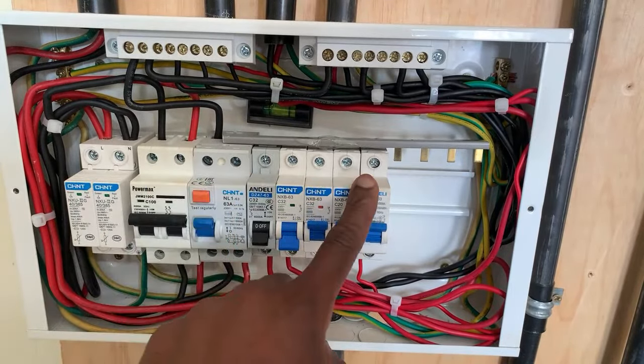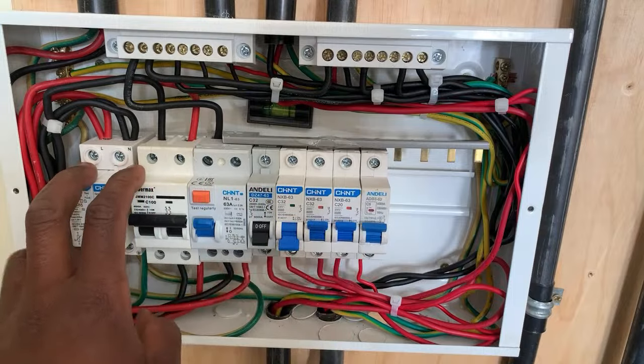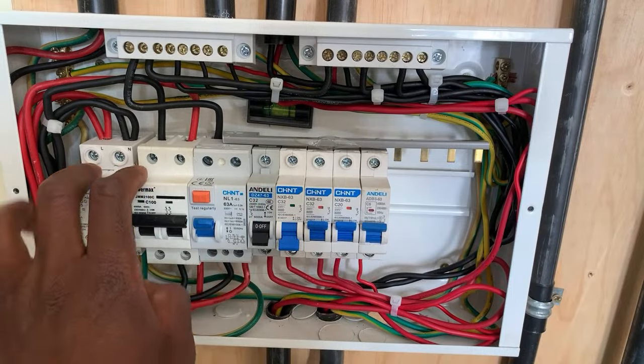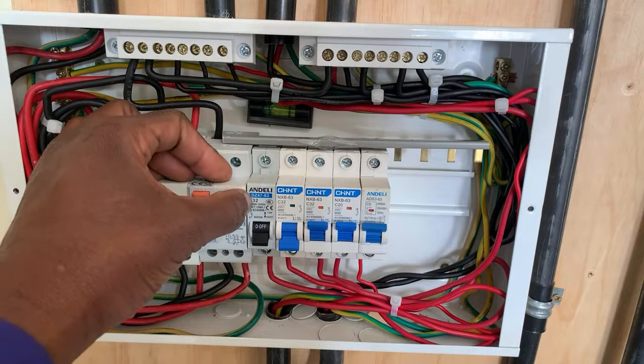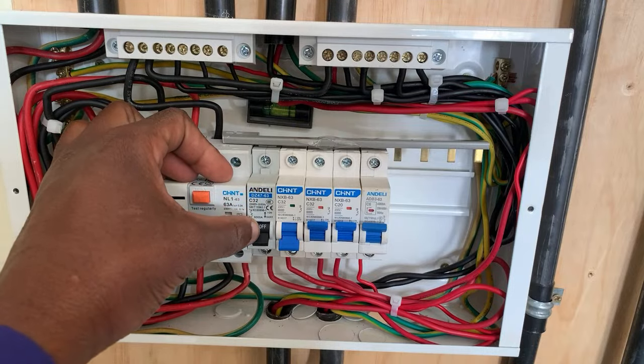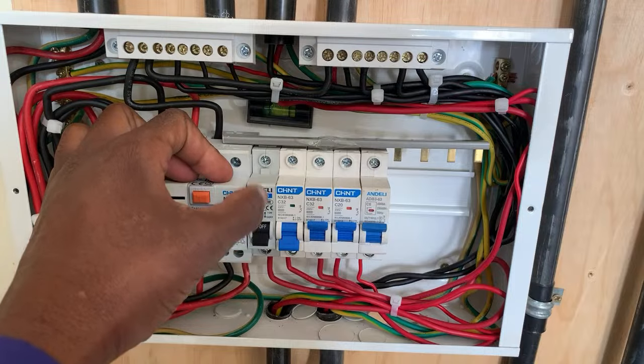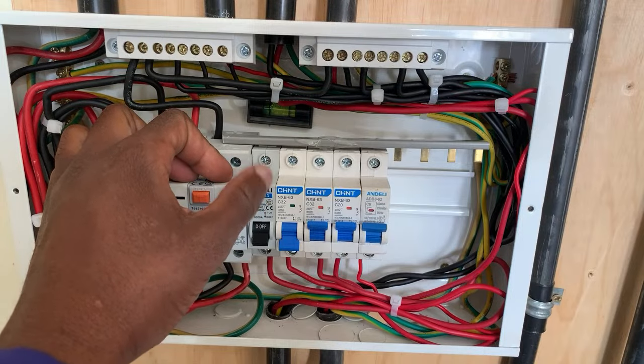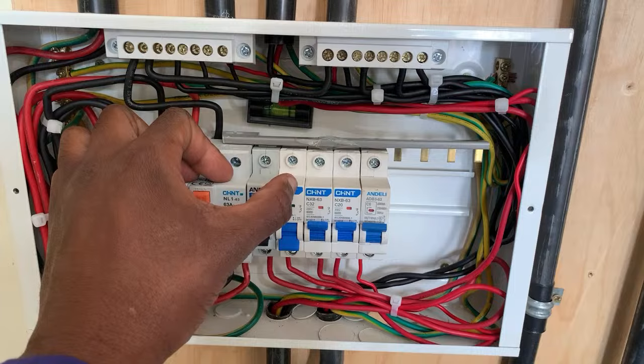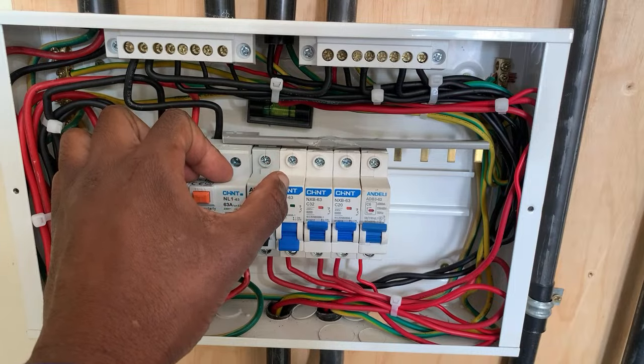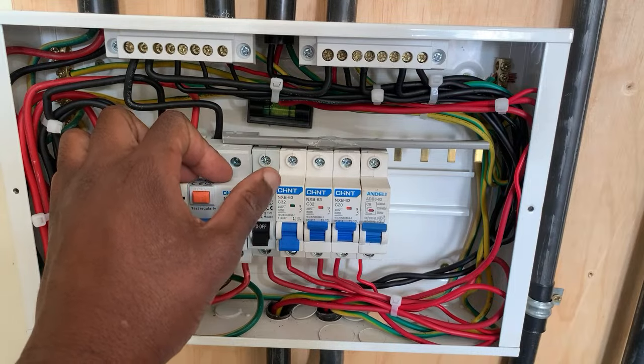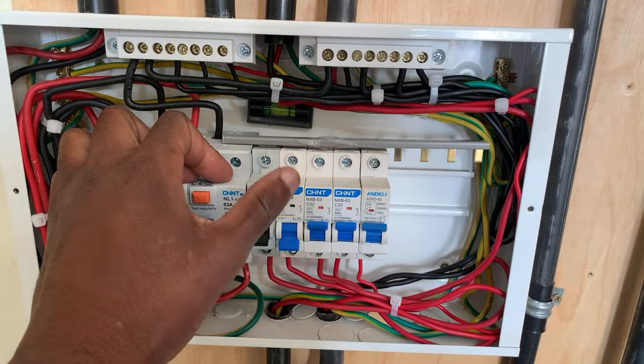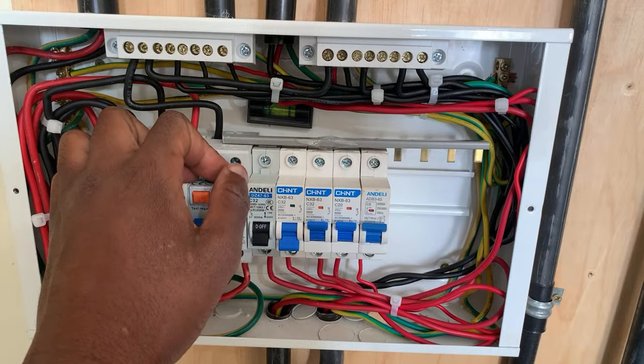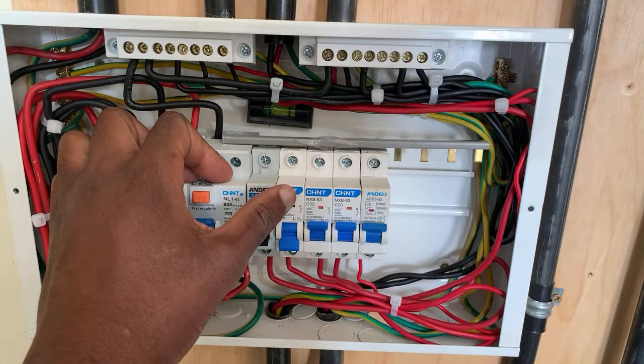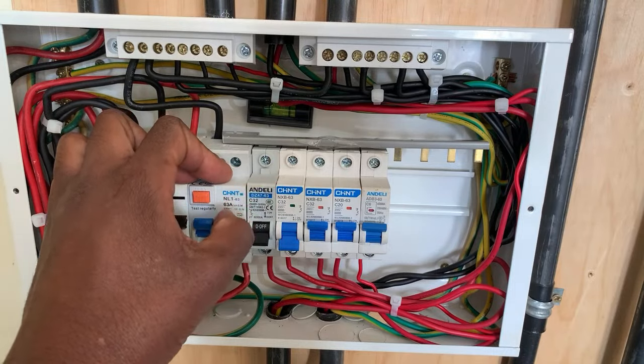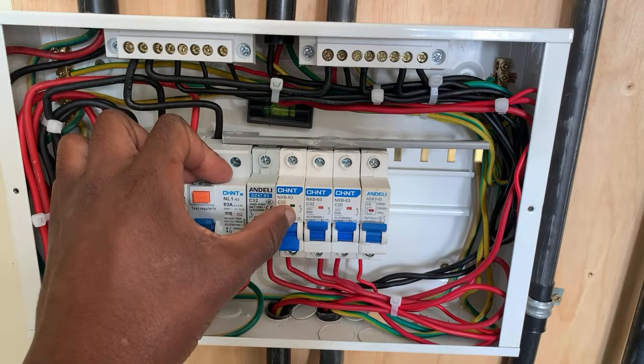So what you normally have to do is to check in the house what is not working. If this is a 32 ampere circuit breaker, there's a high chance it is connected to high powered appliances. Number one, the electric cooker. Number two, it could be the instant shower head. And there could be a heater there. Or probably you have a pump in that house which is connected to a certain socket. It will definitely be dedicated to a 32 ampere here.